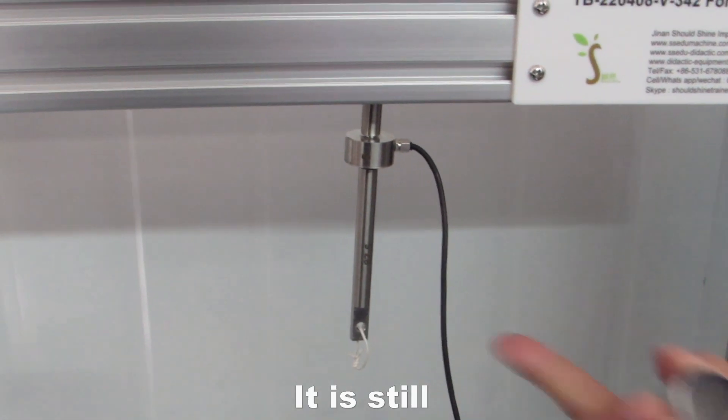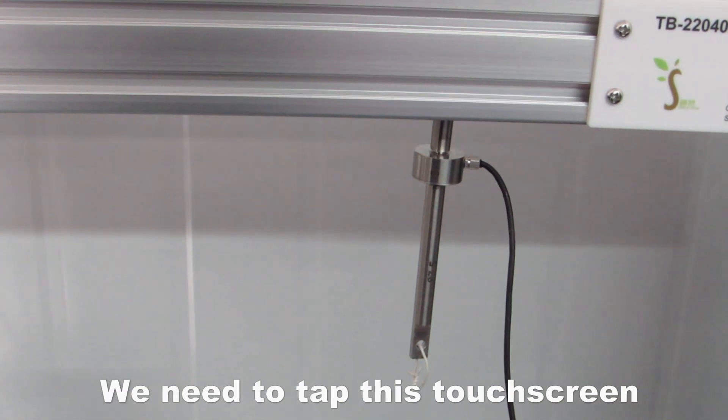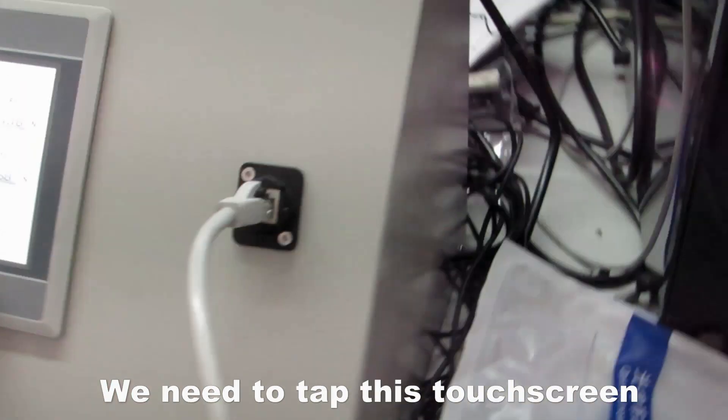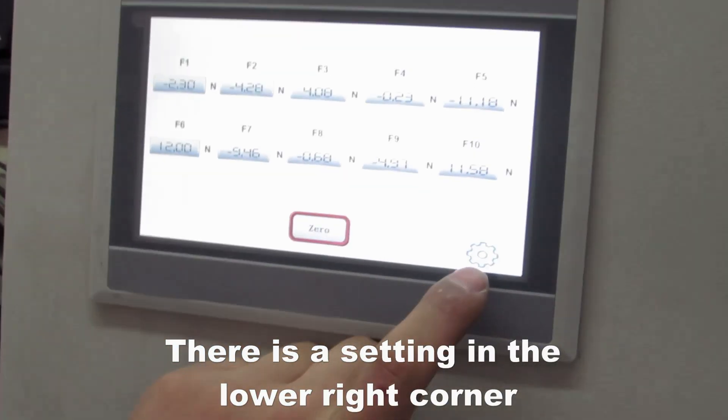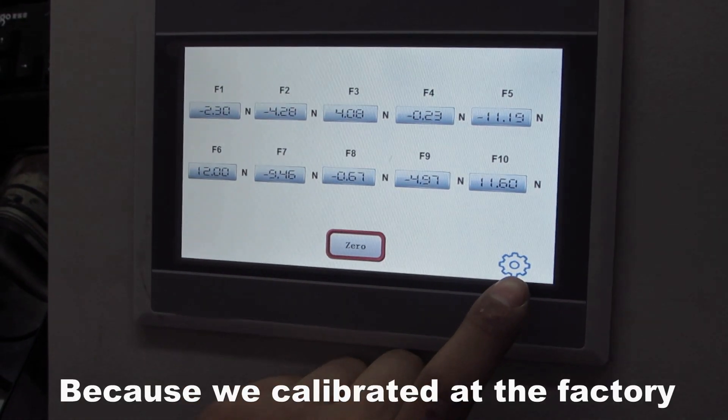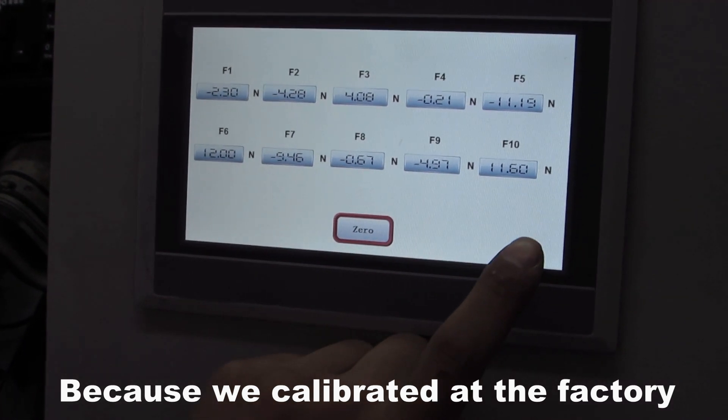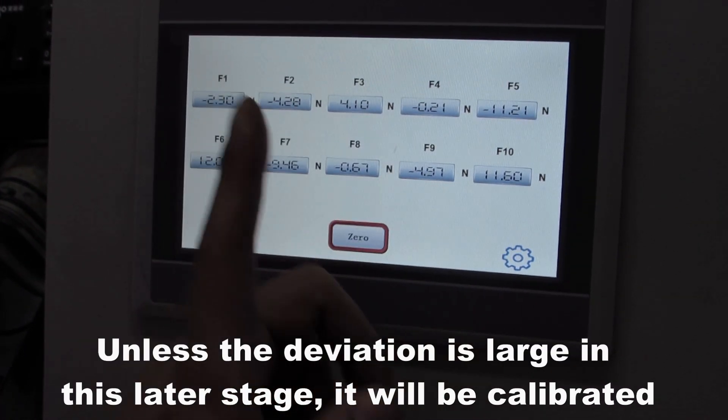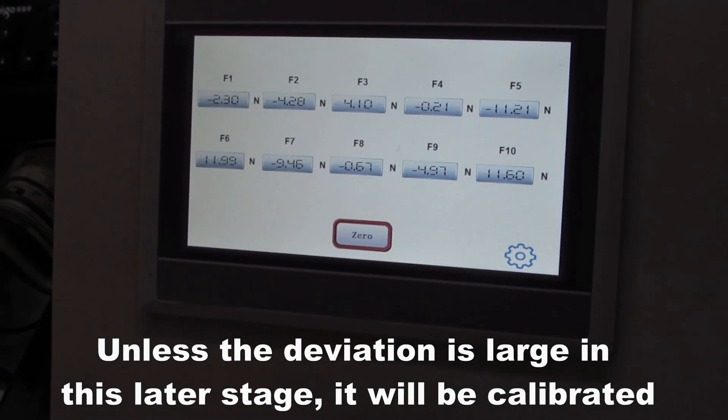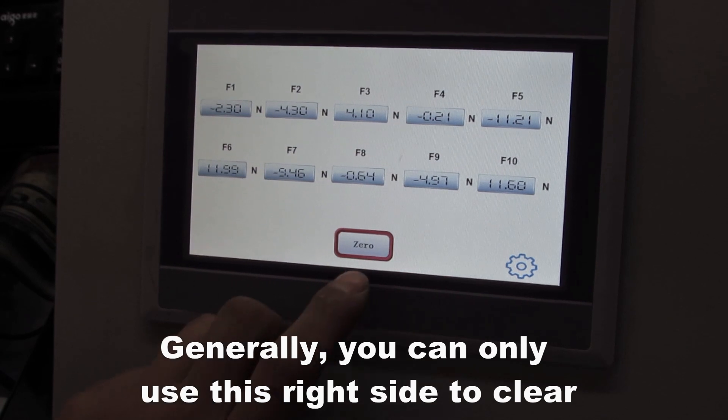It is still in the state without weights below. We need to tap this touch screen. There is a setting in the lower right corner. This setting is usually not used because we calibrate it at the factory, unless the deviation is large in this later stage. It will be calibrated generally.